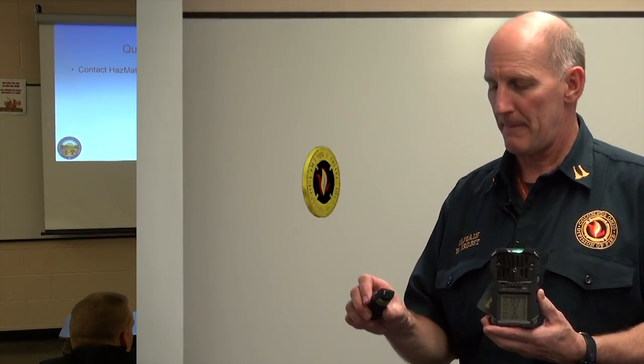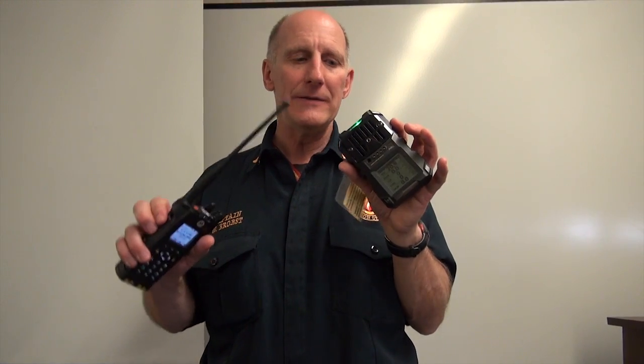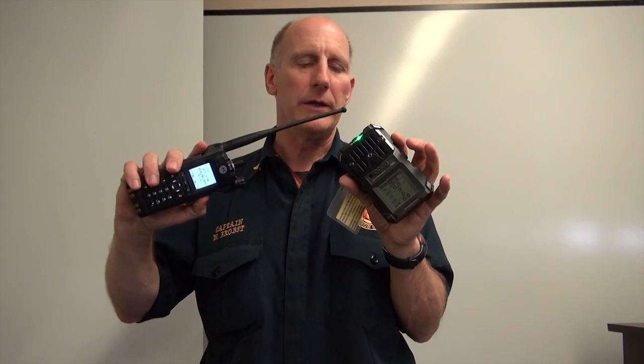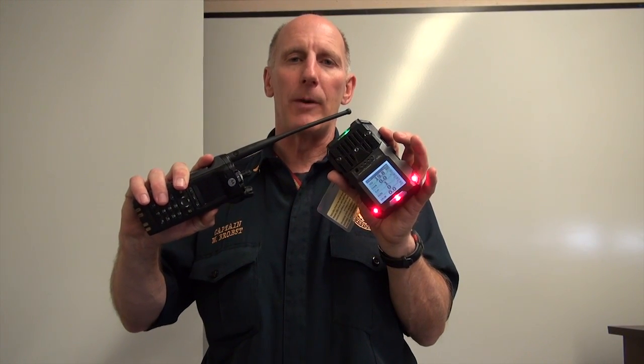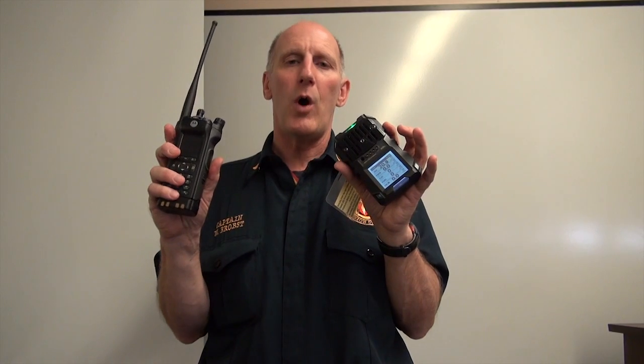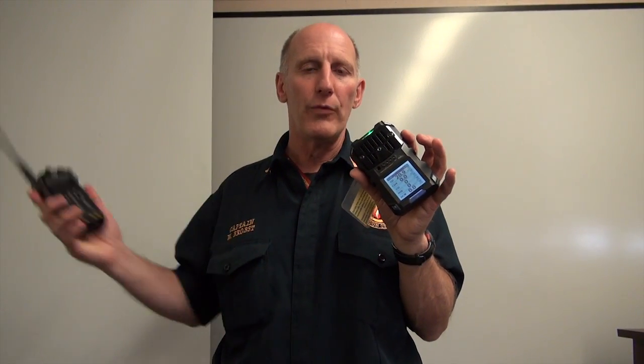Hey, as an additional note, remember, part of intrinsic safety is also the fact that the units can sometimes have interference from radio waves. So if at any point, when you key the mic of your walkie-talkie, you suddenly get an alarm on the instrument, it is simply your walkie-talkie. It's the interference. Typically, if you hold the microphone or walkie-talkie away from the unit, you're less likely to get that. But also, if you're inside a confined space, keying the mic will likely set the unit into an alarm. Once you release the mic, the alarm will clear. So don't allow that false alarm to cause you problems.